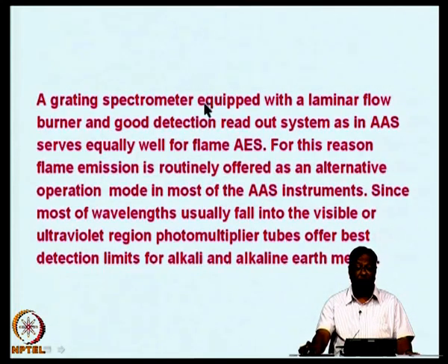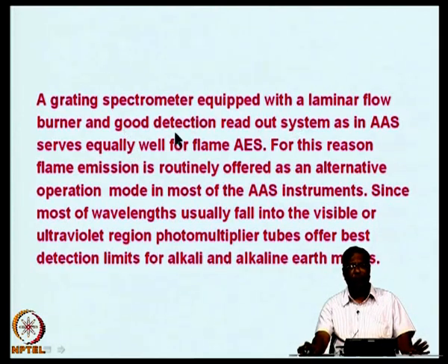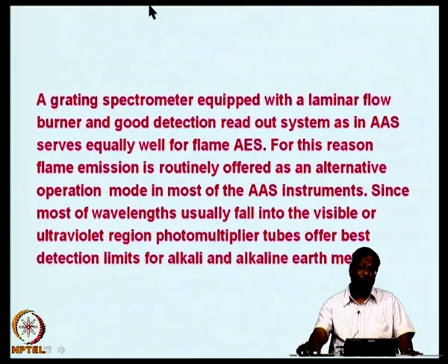So, a grating spectrophotometer equipped with a laminar flow burner and good detection readout system as in AAS serves equally well for flame atomic emission spectrometry. For this reason, flame emission is routinely offered as an alternative operation in most of the atomic absorption instruments.